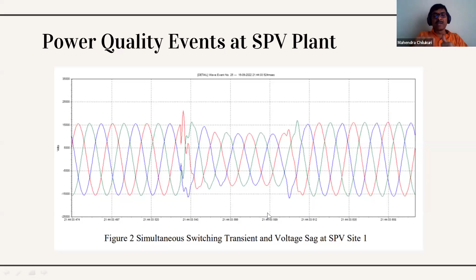Now here is the summary of our power quality audit. You can see that when we monitored power quality for one week, we had dips and voltage variations, slow or fast. We have swells. But look at the transients. Every day so many transients are happening, positive and negative. You can see the date also. But remember, they are not causing any failure. But remember, these transients are going to create stress on the insulation.